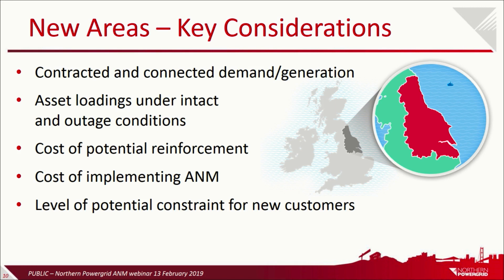So the key considerations for us are, firstly, the amount of contracted and connected demand or generation, because an ANM scheme could be associated with an area where we've run out of demand capacity and would have to reinforce to connect more. But primarily, at the moment, the drivers on the network are to do with where we have excess generation rather than excess demand. This whole presentation is focused towards generation, but the principles that we talk about here can be equally applied.